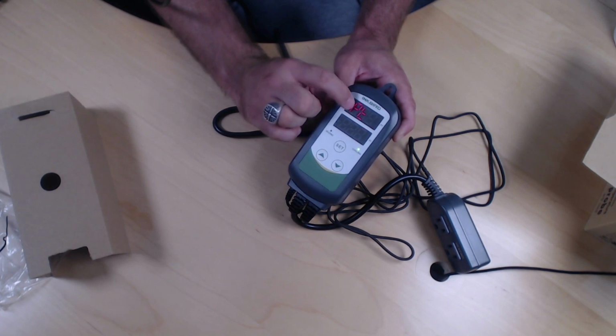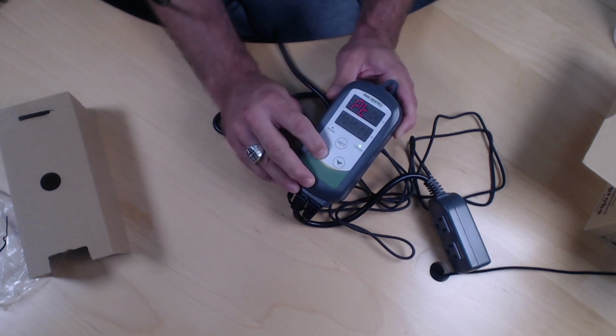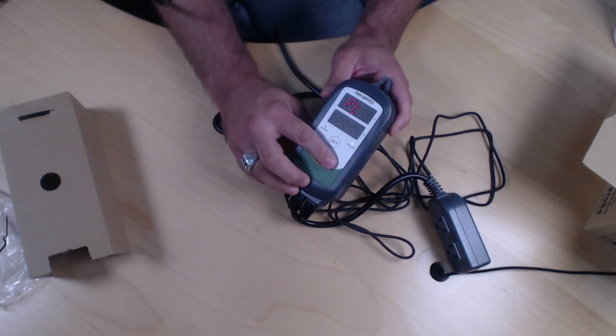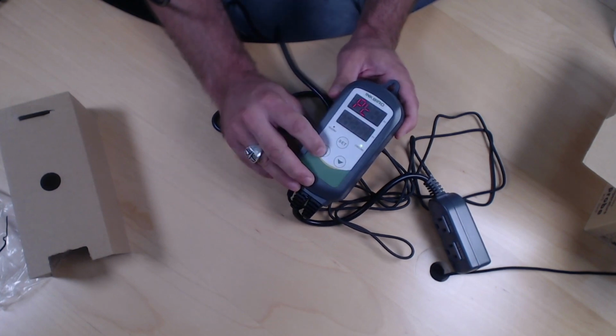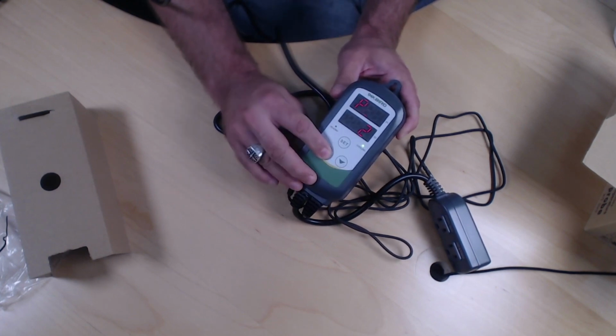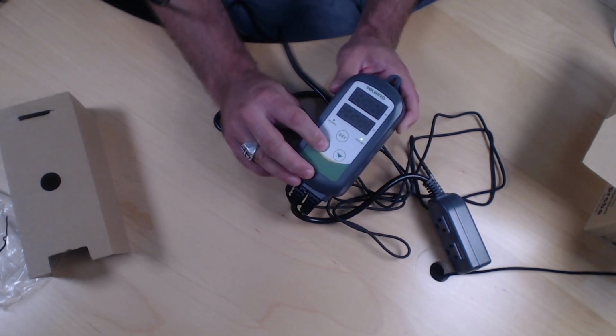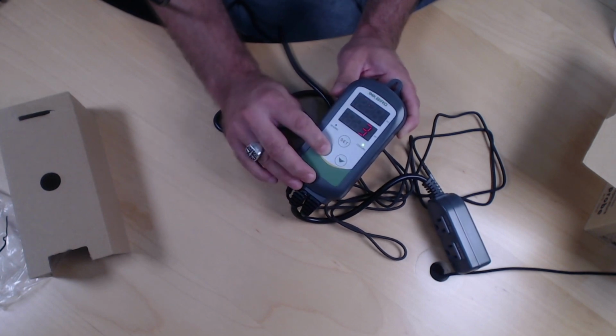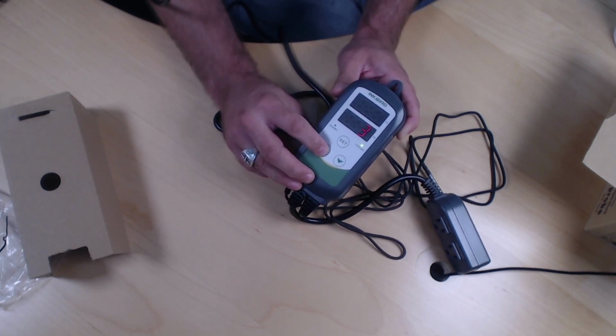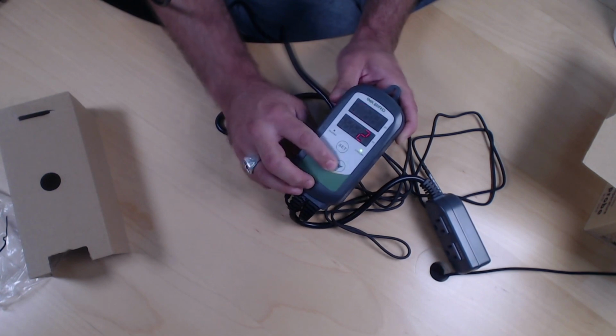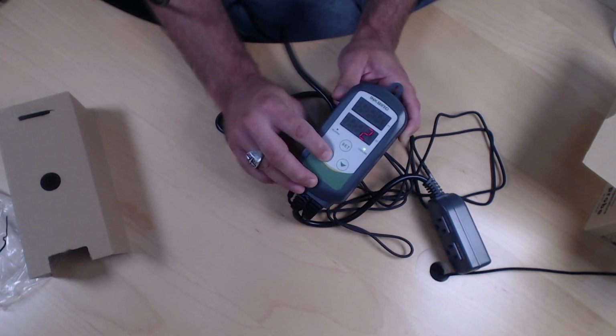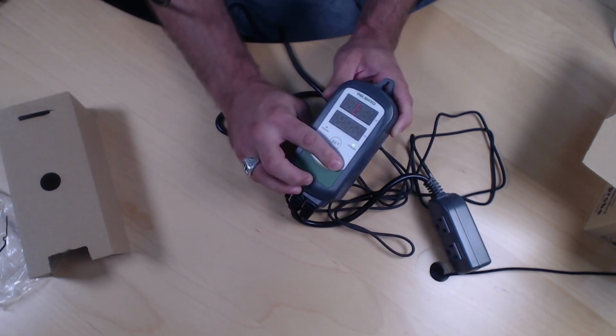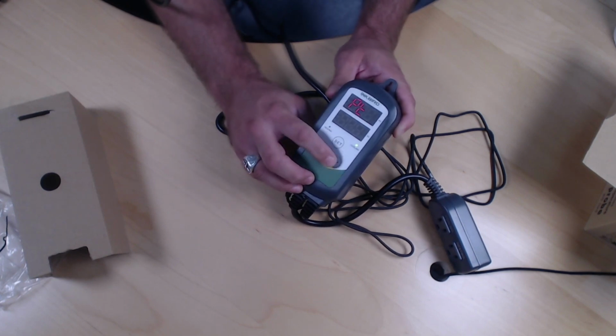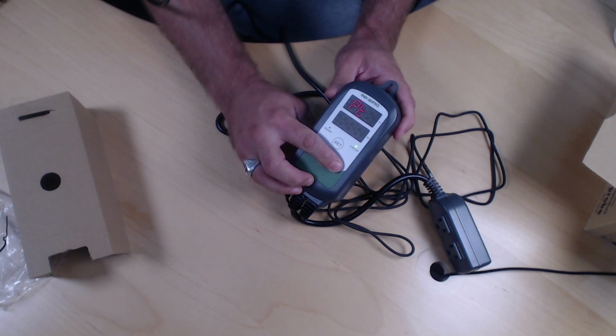This is one of the most appreciated features that I have on this device. PT is the compressor delay time. It is configured in minutes, so whatever you set this at, that's how many minutes it's going to delay your compressor from starting back on. The reason this feature is great is because it's going to prevent your fridge's compressor from turning off and on and off too quickly, because that's too taxing on the compressor and it will lead to your fridge dying sooner than it needs to.